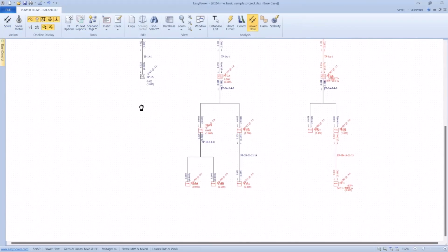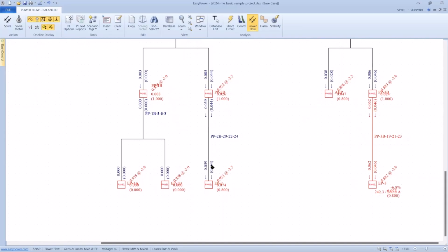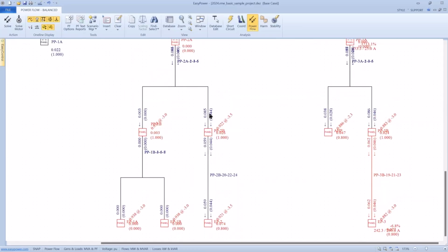and what we're looking at is real and imaginary power. Now the problem is we don't have any loads on all of these panels, but the ones that we do, we see we're supplying 59 kilowatts and 44 kVAR to this particular panel. Now the fact that these are red is indicated by these icons here on the top left. On the second row, we have overloads. We're showing overloads for current. They will be because this icon has been set.